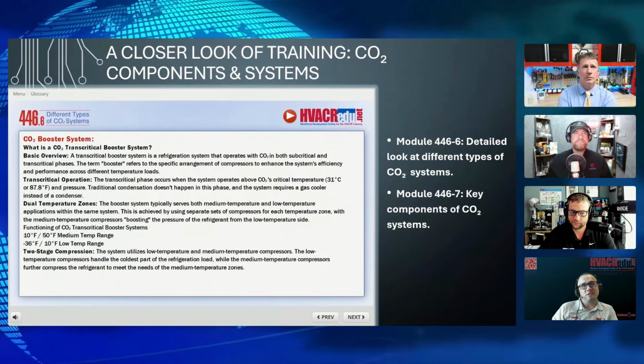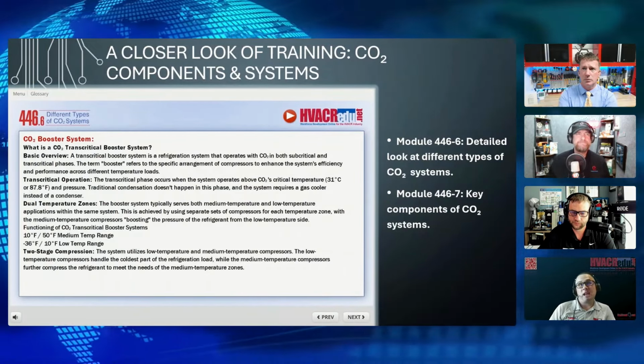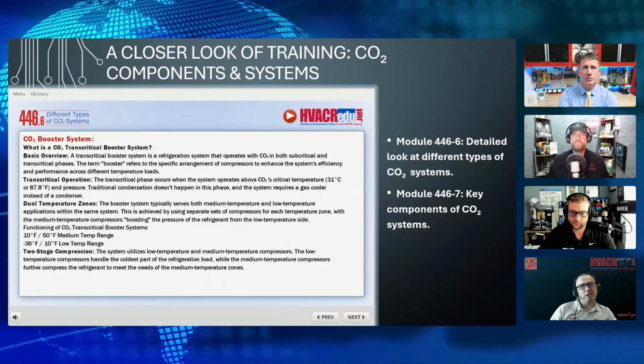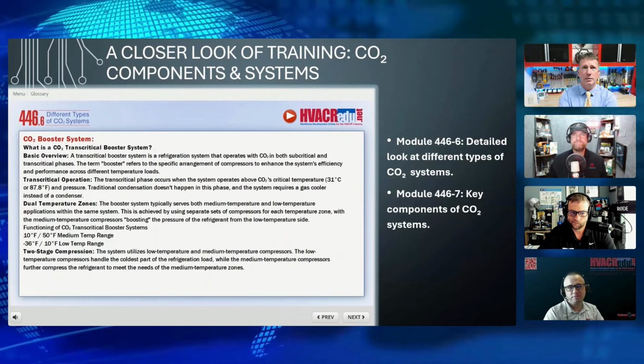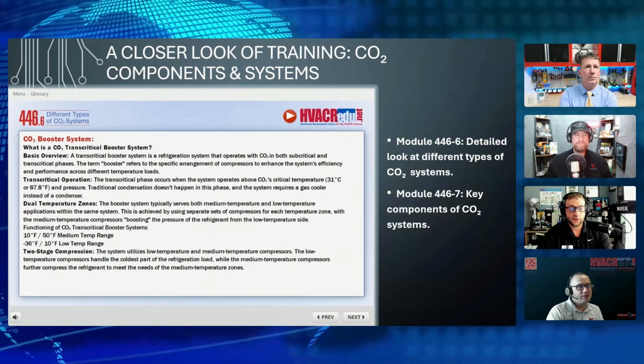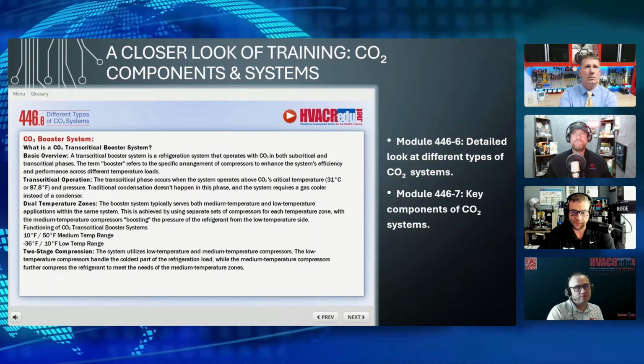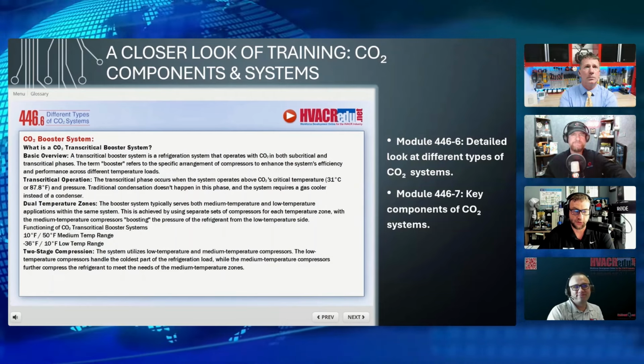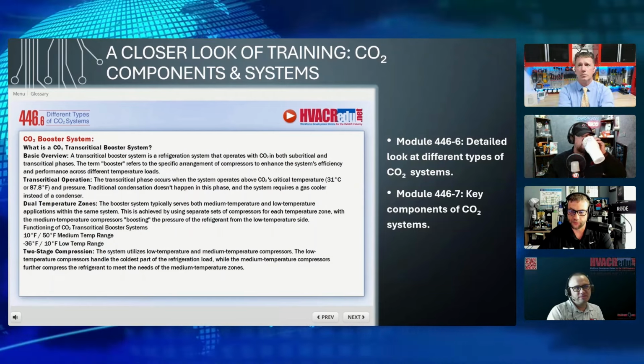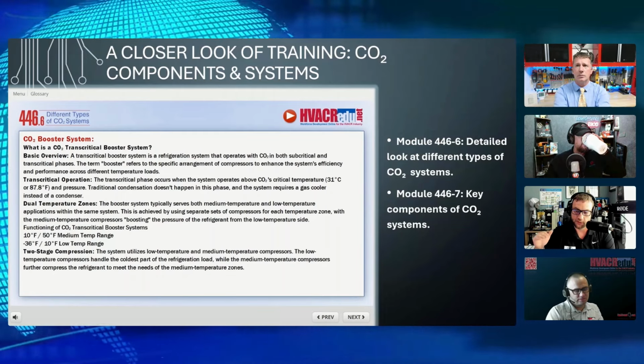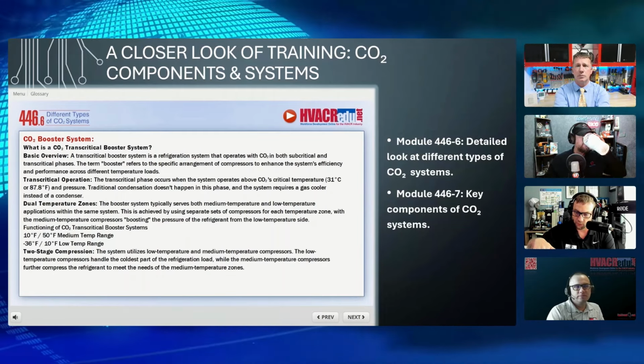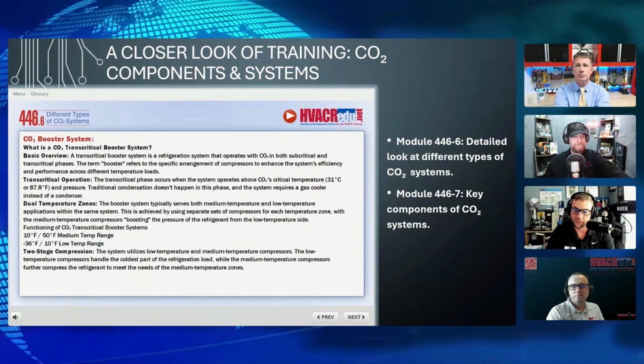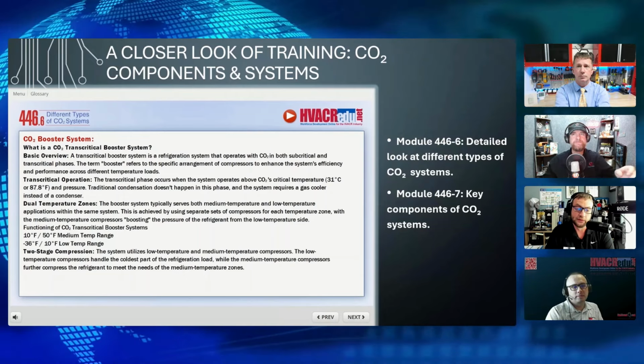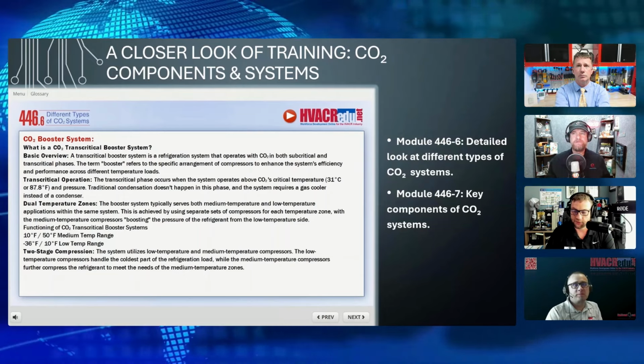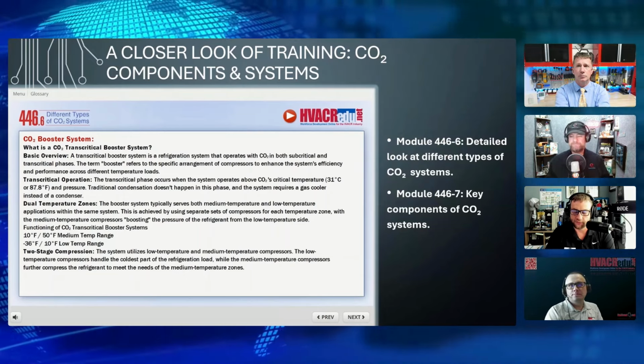So again, we're going to dive into 446-6 and 446-7, CO2 systems and components. Just a little 30,000 foot view of what's in here. Go ahead, Brett. So, transcritical booster system, I basically explained it, giving you what a booster is. A booster system is one where we're taking the discharge of the low temp compressor and putting that into the medium temp suction, working in the transcritical range, which I touched on briefly.